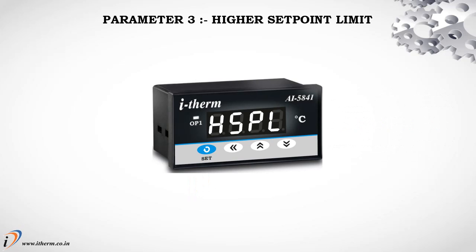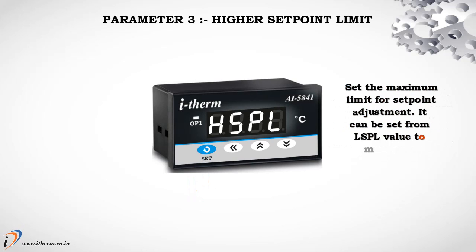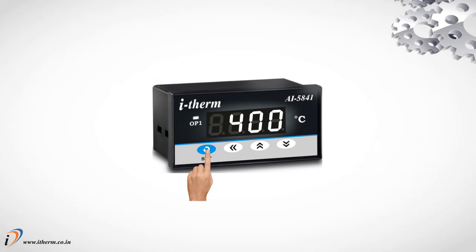Parameter 3: Higher Set Point Limit. Set the maximum limit for set point adjustment. It can be set from the L SPL value to the maximum specified range of the selected sensor. Default H SPL value is 400.